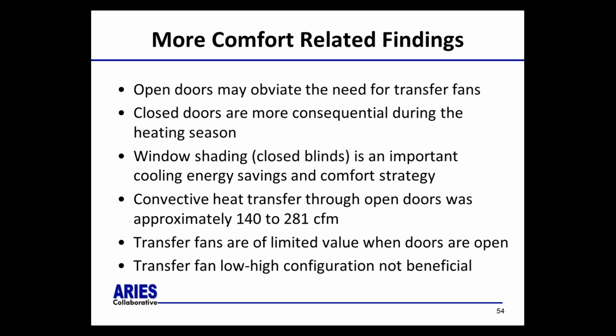I'll talk in a second about our experiments in heating climates. Window shading — we closed the blinds and looked at variations in the amount of sunlight coming through the windows. That does prove to have, as you'd expect intuitively, a real benefit in terms of cooling energy savings. Again, it's a customer-implemented measure, so it's undependable, but it does make a difference in energy use and comfort.